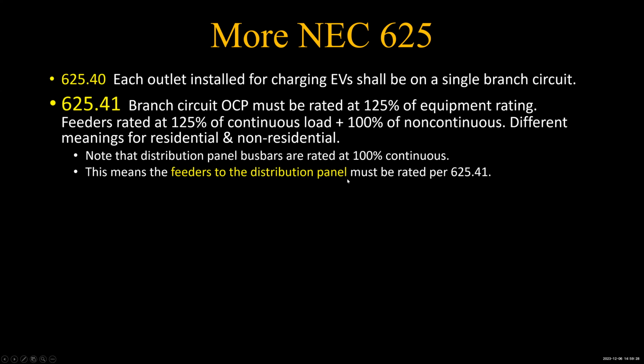In any case, the feeders to the distribution panel must be rated per 625.41. All right, not the main circuit breaker, not the bus bars, but the feeder wire. All right, and let's go back then to the 625.41. 125% of the equipment rating. All right, so let's say you got one of those 40 amp chargers, and then you have to take 125% of that, that's 50 amps.